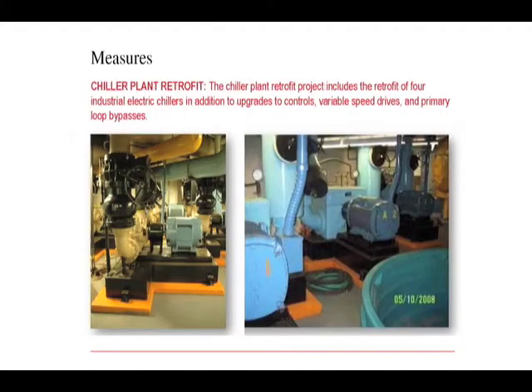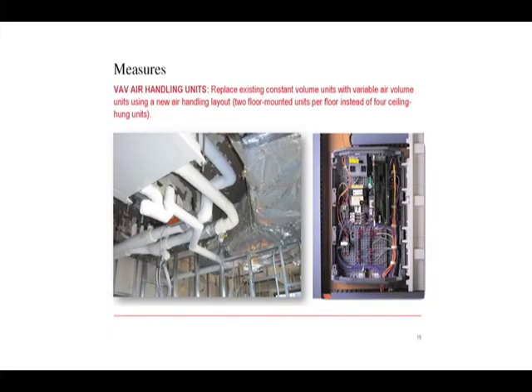By controlling pumps and fans throughout the system, and louvers, you're directing the cooling where it's needed. Controlling the radiators digitally rather than just with your typical screw, even if that typical screw has a thermostat attached to it. What does that mean? You're only using as much energy as you need, when you need it. At sunrise, the person on the west side of the building isn't going to be frying. At sunset, on the west side of the building, excuse me, isn't going to be freezing.